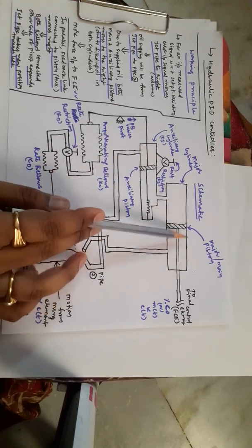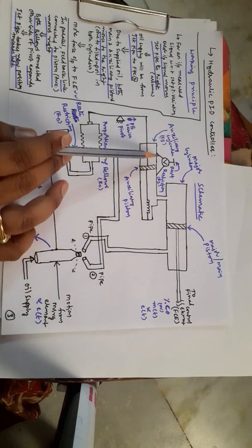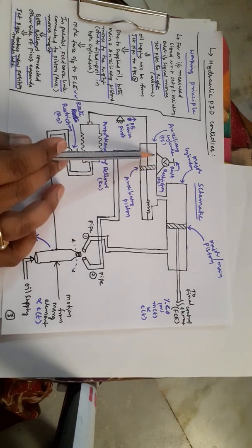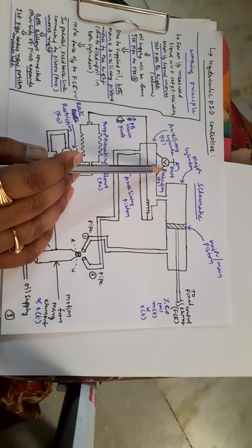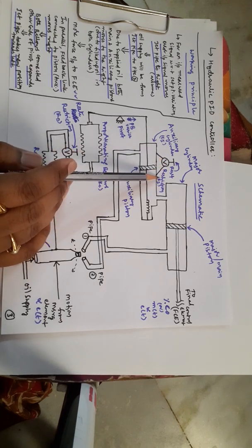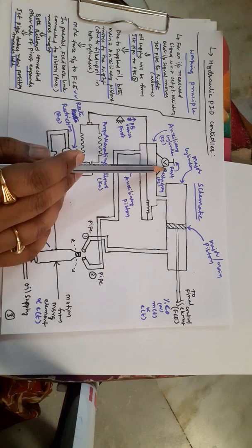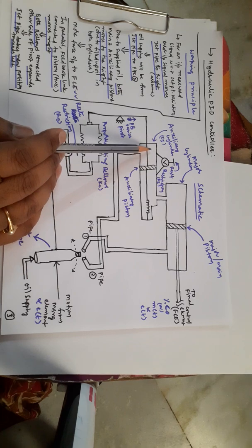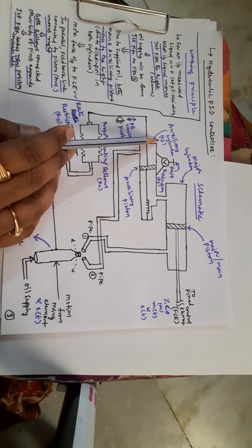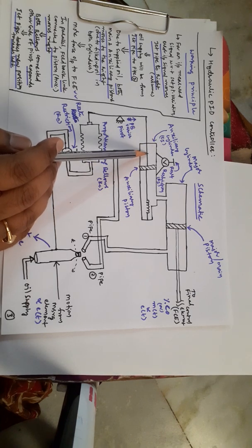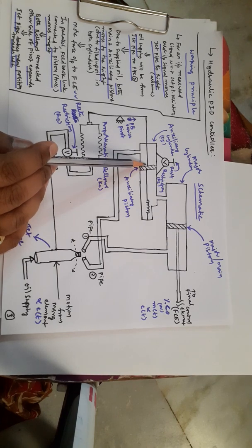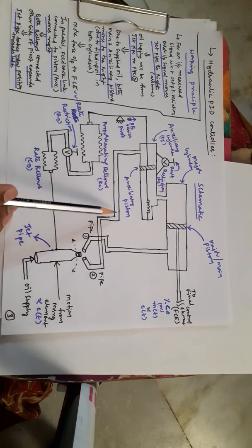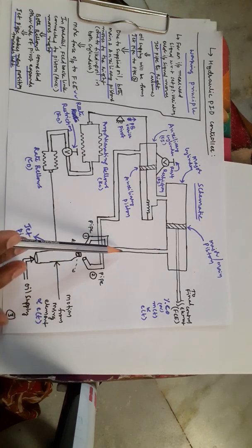This component is referred to as the auxiliary cylinder. The main use of the auxiliary cylinder is to obtain an output in terms of integral action. For integral capacitance we require a storing capacity, and for resistance we require a restriction. This valve is the reset restriction valve, giving an R_I value, and the cylinder provides the reset capacitance or integral capacitance. This is the auxiliary piston, whose movement is forwarded to the main piston.